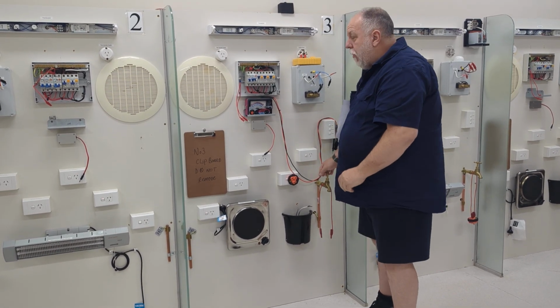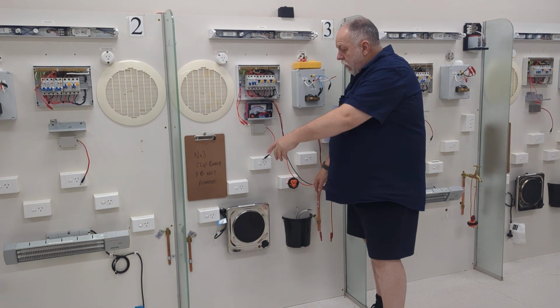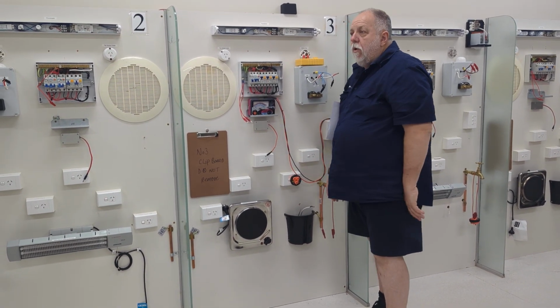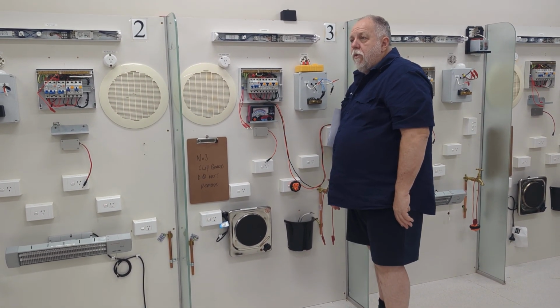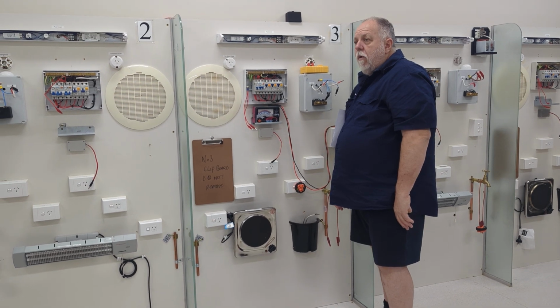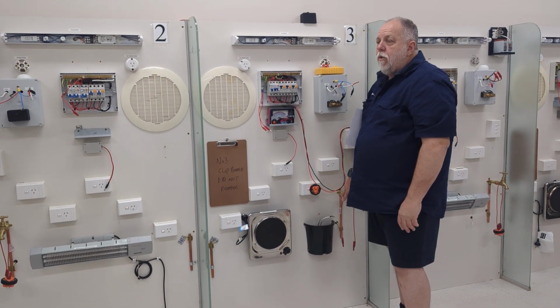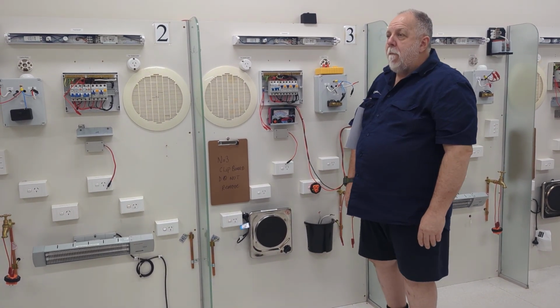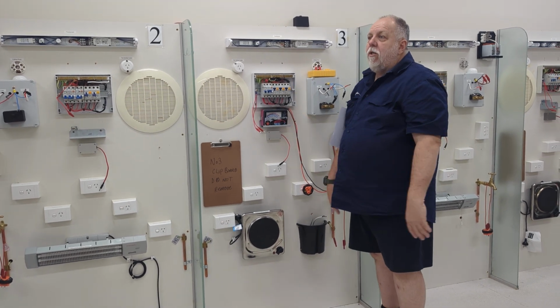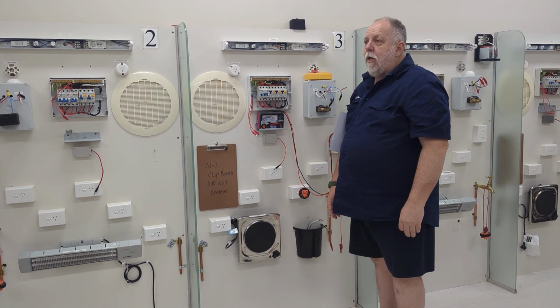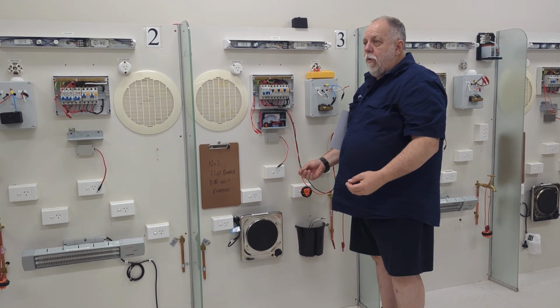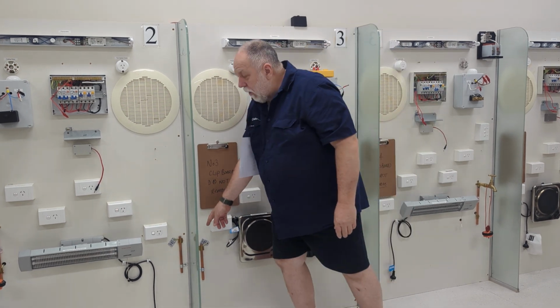The main reason is if you take the bonding conductor off the tap and then remove it, and the main earth is not hooked up, it's disconnected out of the circuit. All right? What's the problem with tapware these days? What's the problem with taps these days too? Exactly, there's no continuity of copper or anything. We don't have the continuity going into ground. Our earth stake will go in.